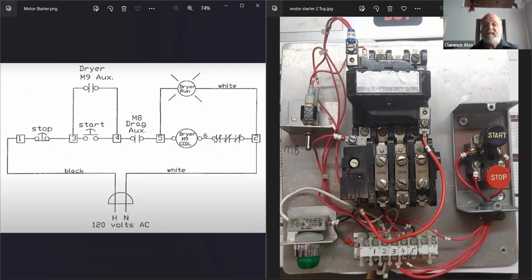Just because it said 0 there doesn't mean you really get 0. You won't know if you get 0 there unless you push the start button, because you've got to see what this coil has on both sides. So when you hit the start button, you're expecting 120 volts here, and 0 volts there. But in this case, when you press the start button, you had 120 volts there. Is that a good or bad reading? On a good working circuit, it's bad — you were expecting 0. So if I have 120 volts there, we can't expect that coil to work.